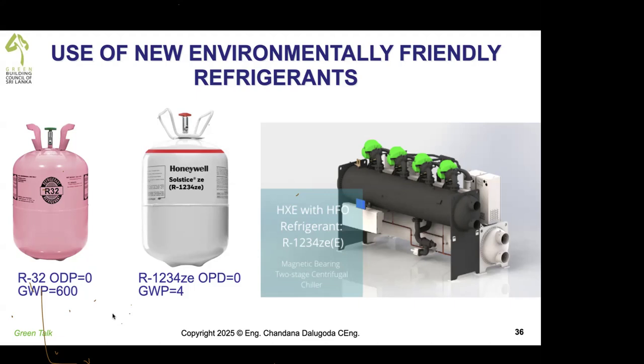Those common refrigerants have global warming potential of 1,000, 2,000, that kind of thing. So the latest refrigerant R32, ODP 0, GWP 600. Then another very latest refrigerant found, R1234ZE, ODP 0, GWP 4. Those are the most suitable refrigerants for chillers. You should use this equipment.